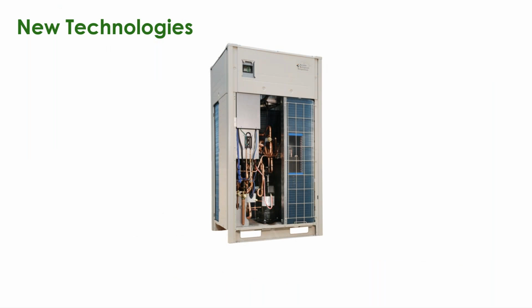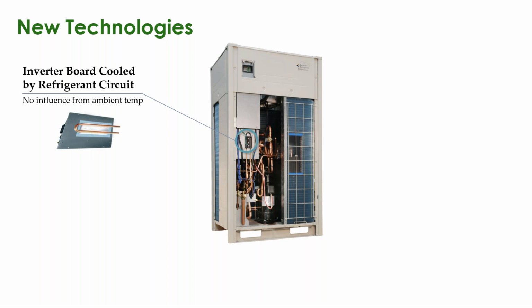And the way they're getting there with these is with some new technologies that have been added over the years. One of those is cooling the inverter circuits with the refrigerant circuit. This allows you to completely seal the electrical area, which through practice was learned that light, dry snow can suck up into electrical components, and when the temperature warms up, miraculously things short out and break. So this allows for better sealing of the cabinet and protection of the electrical components without any influence from the ambient temperature or the ambient environment itself.